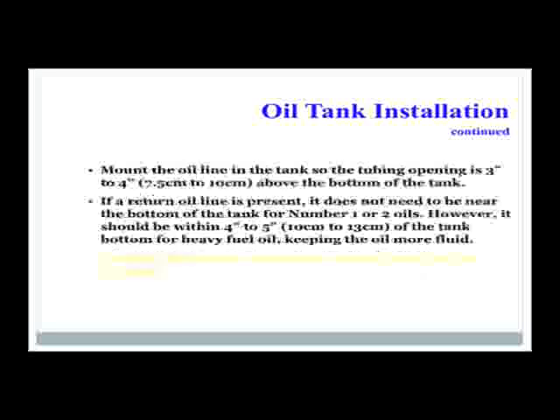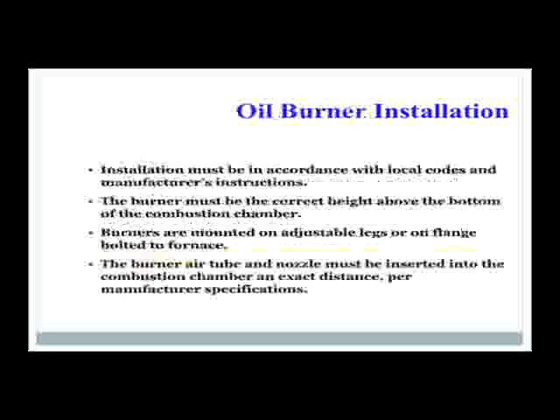Mount the oil line in the tank so that the tubing opening is 3 inches to 4 inches above the bottom of the tank. If a return line is present, it does not need to be near the bottom of the tank for number 1 or 2 oils. However, it should be within 4 inches to 5 inches of the tank bottom for heavy fuel oil, keeping the oil more fluid. Never use compression fittings with fuel oil systems. Again, oil burner installations must be in accordance with local codes and meet manufacturer's instructions.